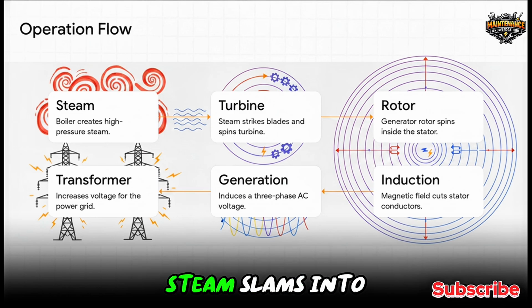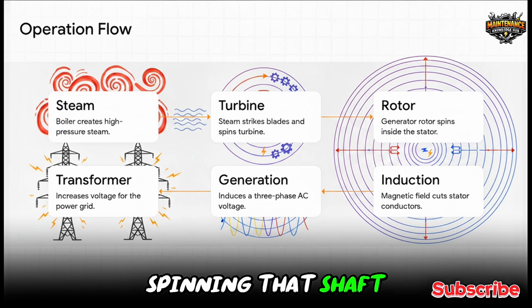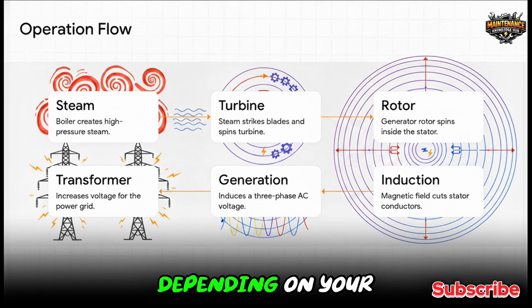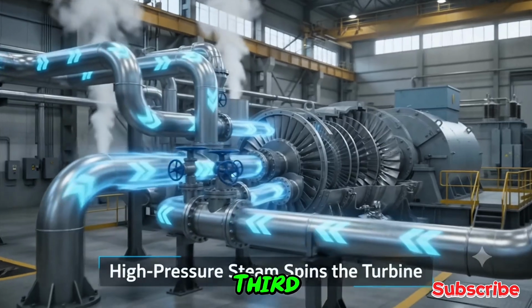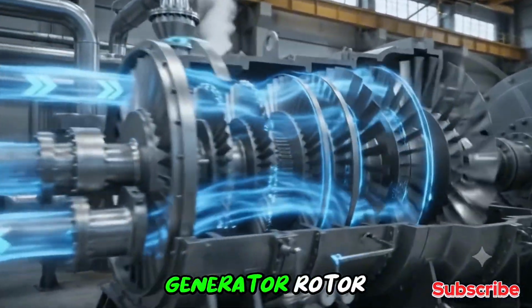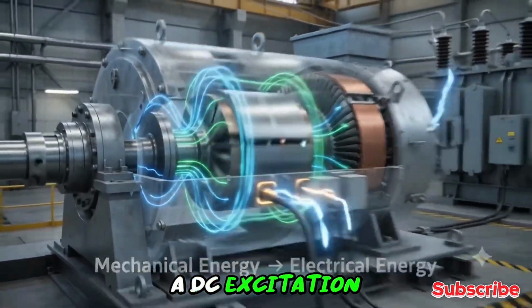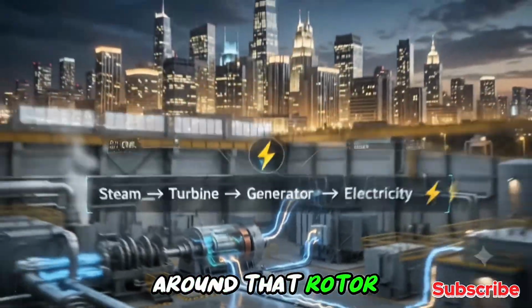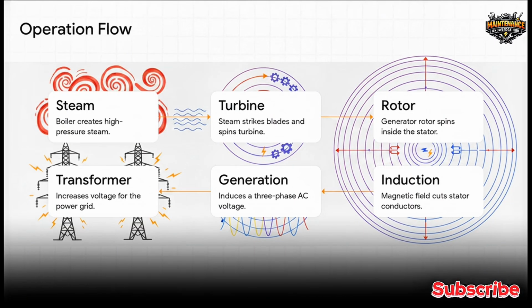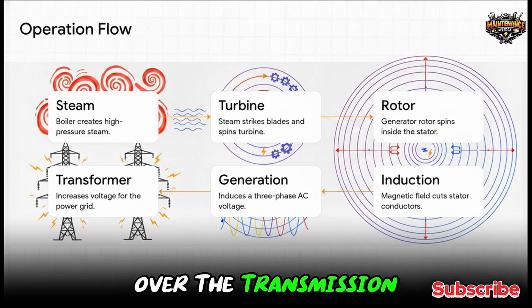Second, this extreme steam slams into the turbine blades, spinning that shaft at 3,000 or 3,600 RPM, depending on your local grid frequency. Third, since the turbine shaft is directly coupled to the generator rotor, the rotor spins inside the stationary stator. Fourth, a DC excitation current creates a magnetic field around that rotor, cutting right across the stator conductors. Fifth, this induces a 3-phase AC voltage, usually between 11 and 24 kilovolts. And finally, step 6. A transformer steps that voltage way up, sometimes up to 765 kilovolts, so it can be blasted out over the transmission network.